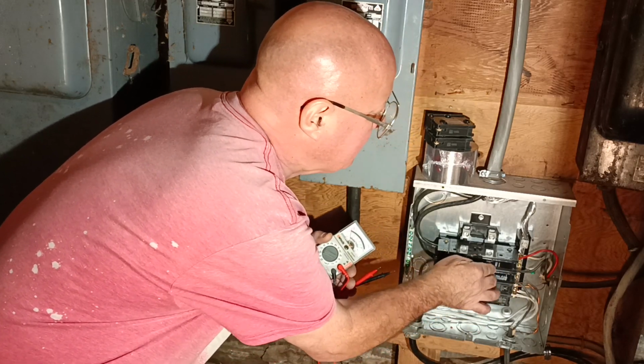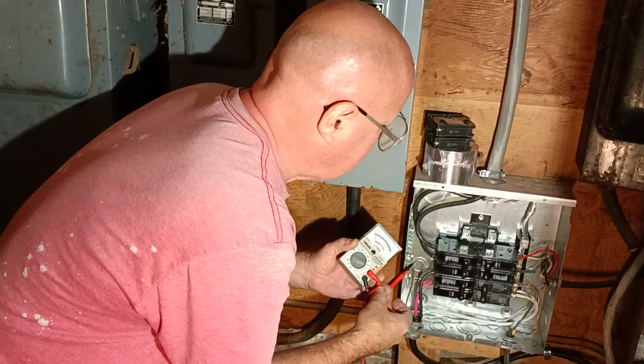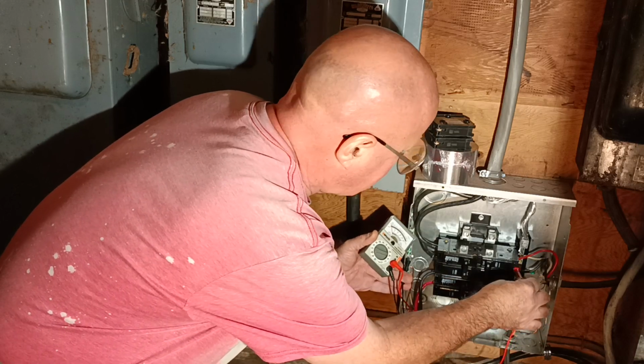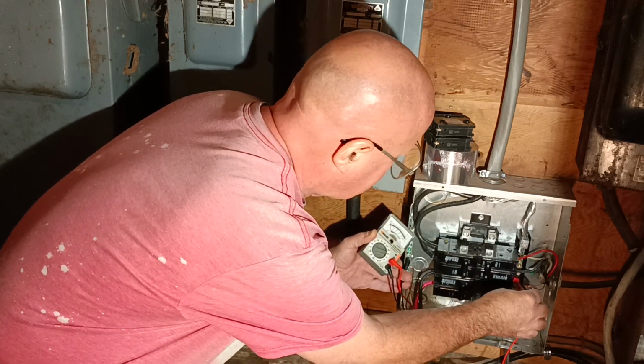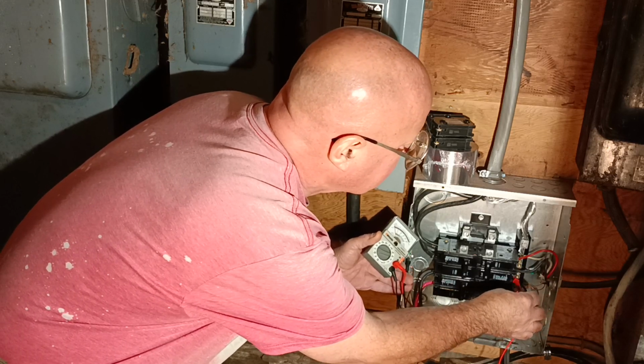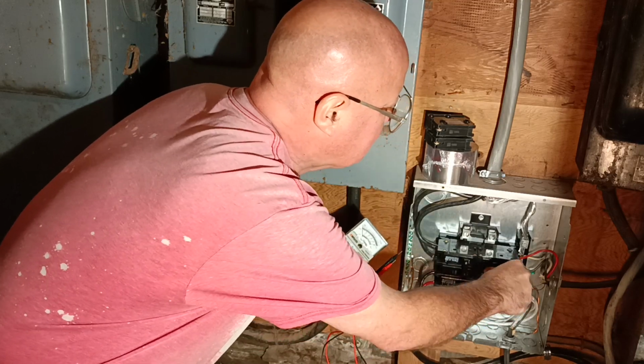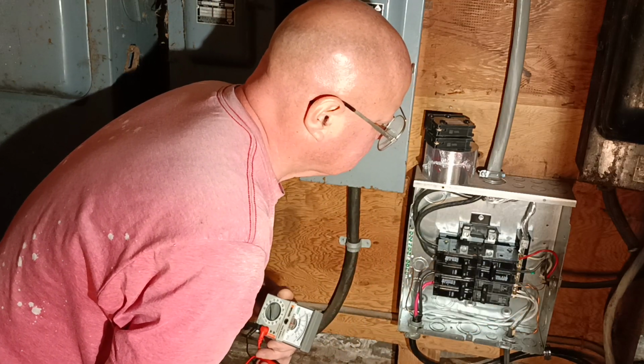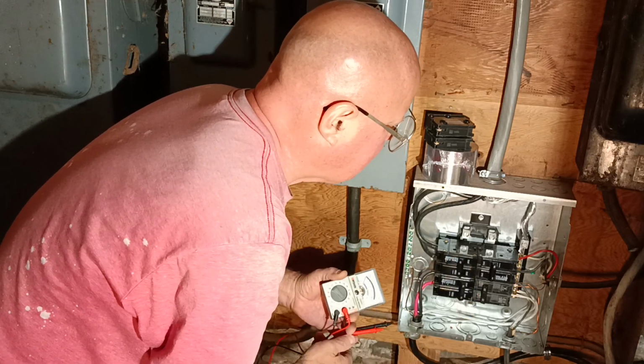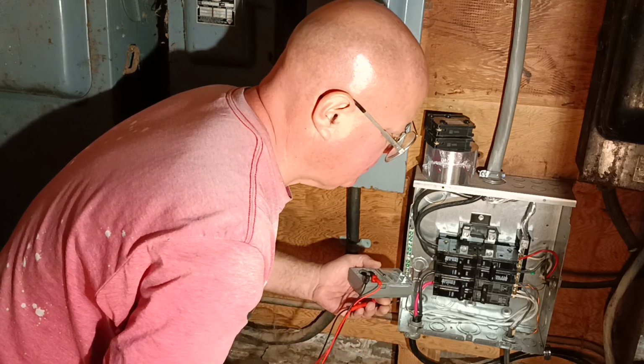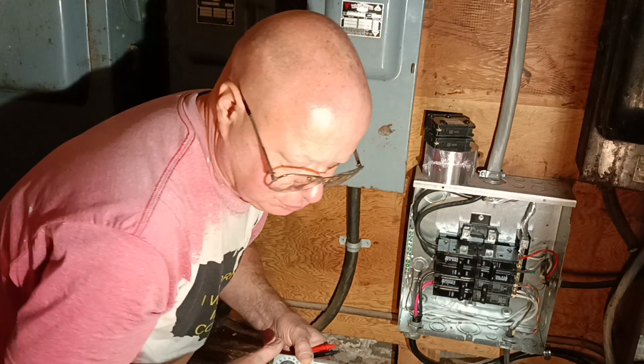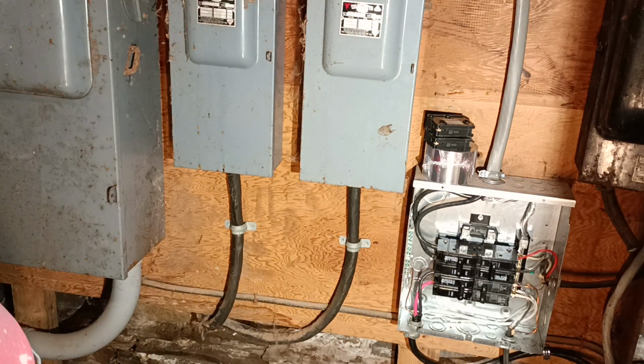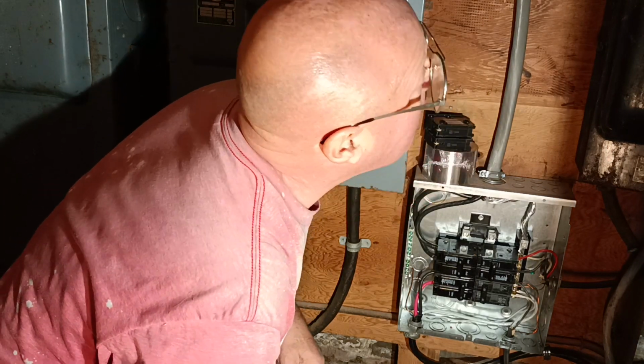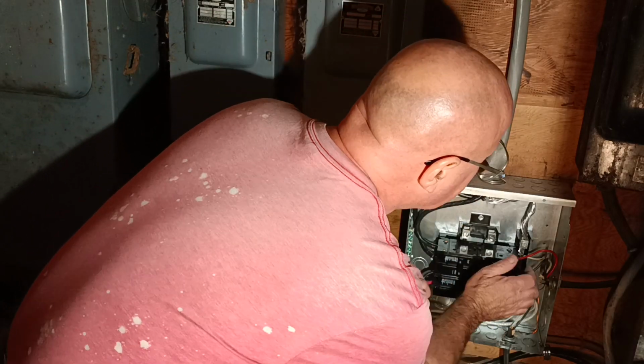We'll try turning it back on. And we'll check it again. Still no power on either leg. So we'll turn off our 100 amp main and we'll put a new 30 amp breaker in here. Okay, we have our 100 amp off. We'll pull this out.